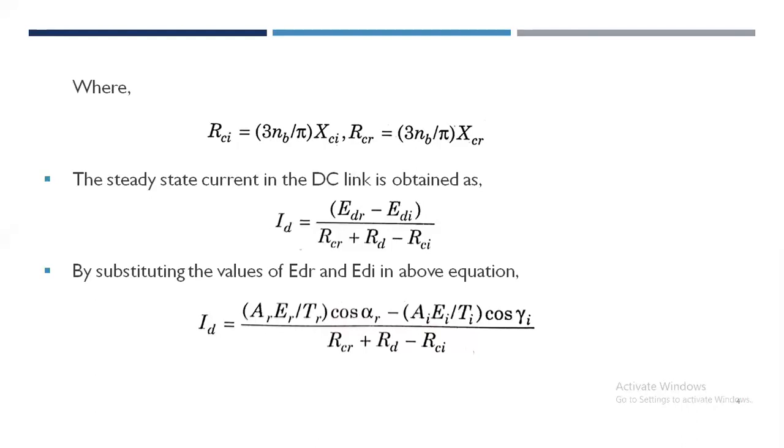It is also to be noted that current control at the inverter worsens the power factor at the higher loadings, as the extinction angle has to be increased. Increased extinction angle also implies higher losses in the valve snubber circuits. The operation at minimum extinction angle at the inverter and current control at the rectifier results in better voltage regulation than operation with the minimum delay angle at the rectifier and current control at the inverter. This is valid for similar values of RCR and RCI.